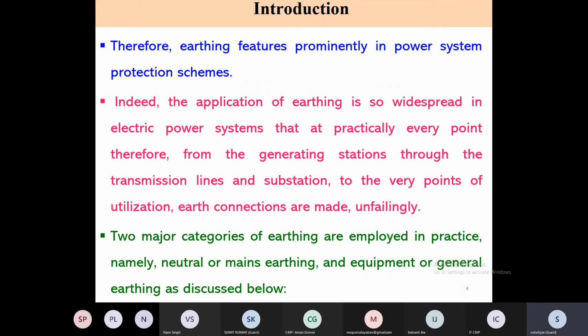Now, the protection system is a system which will scan the voltage and the current flowing through the power system. As long as the insulation is good, the voltage and the current of the power system will be as per specification, or the normal voltage and normal current. Whenever a fault occurs, the electrons will penetrate the insulation going to the ground, and then when it returns from the neutral, there are current transformers which will scan this current and disconnect the faulty equipment from the power system.